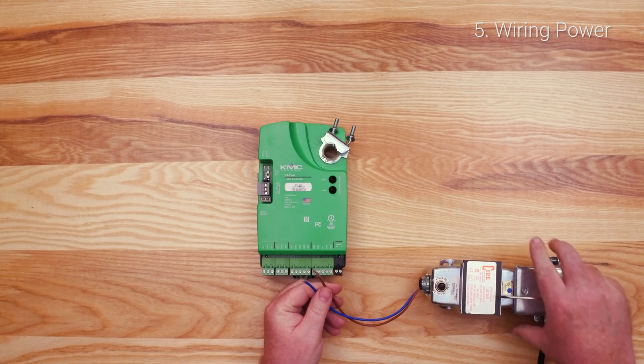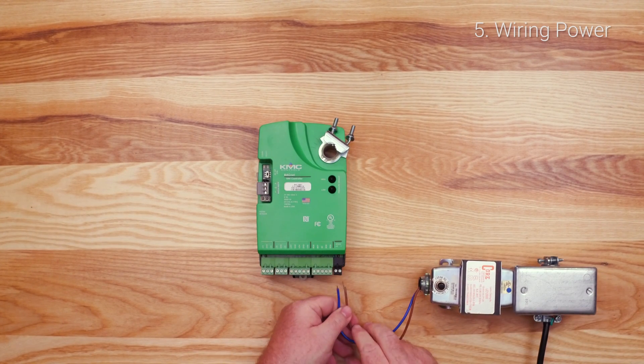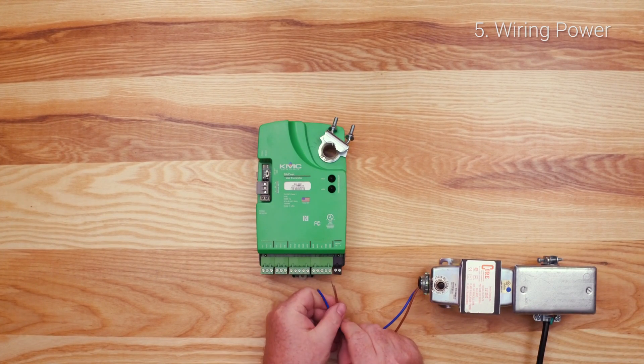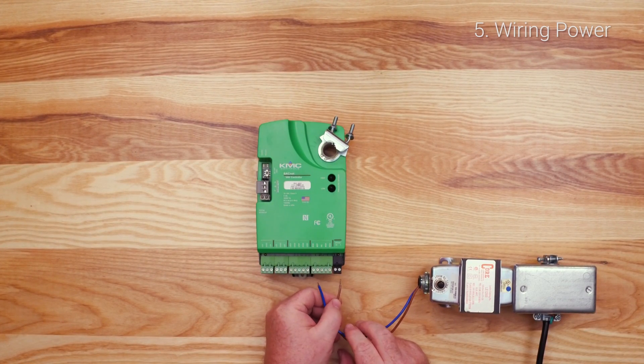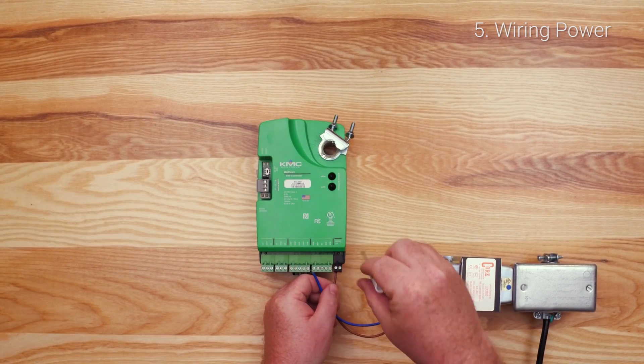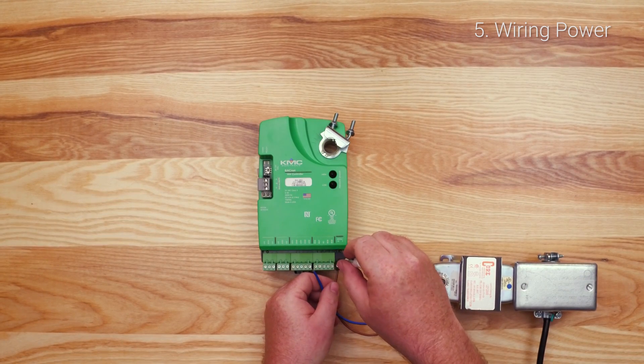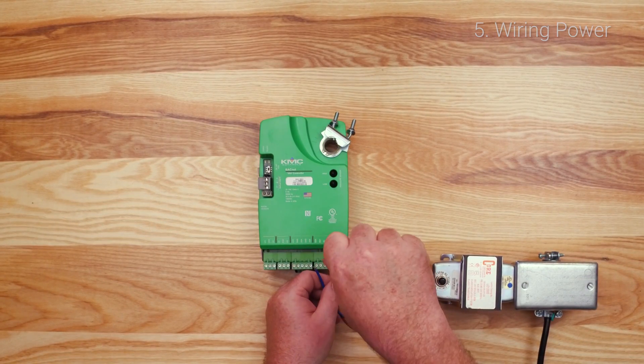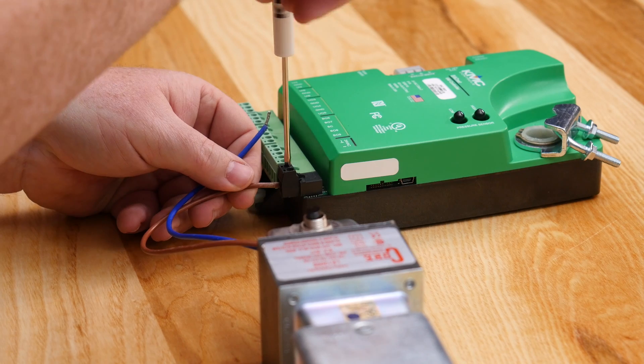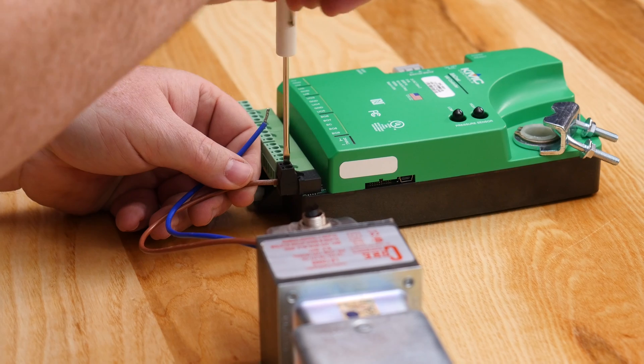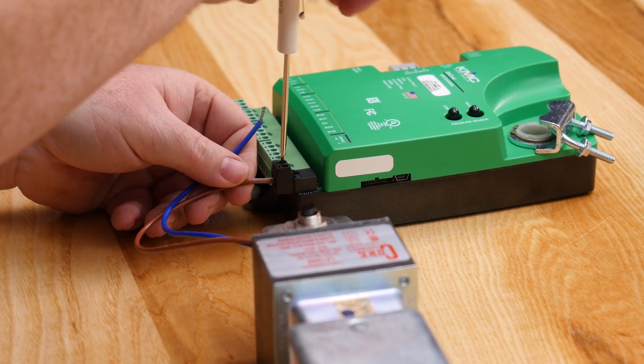The last step in wiring a BAC-9000 series controller is to connect the power. When connecting power, it is recommended that you use 12 to 24 gauge copper wire. Connect a 24 volt class 2 transformer to the black power terminal block of the controller. The transformer should be dedicated to this controller.